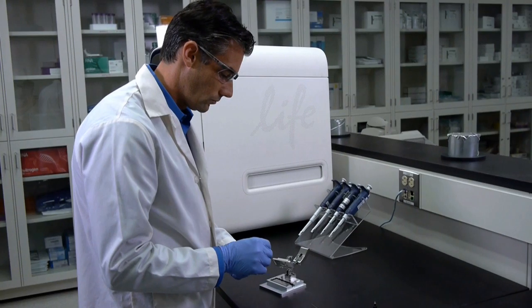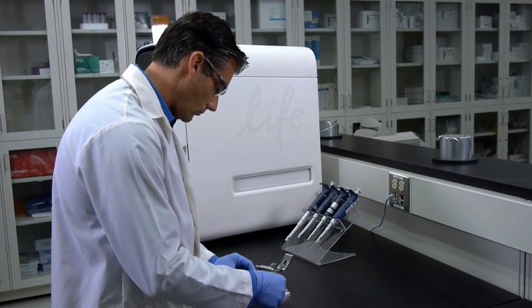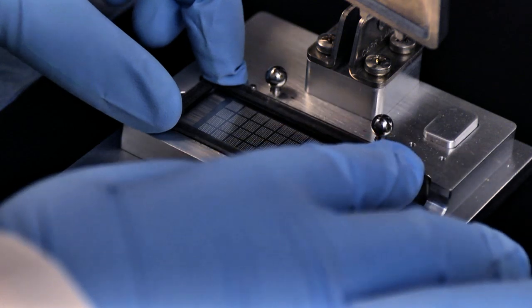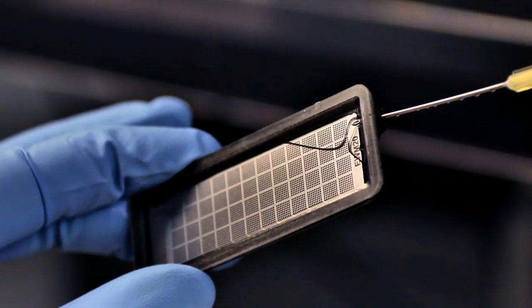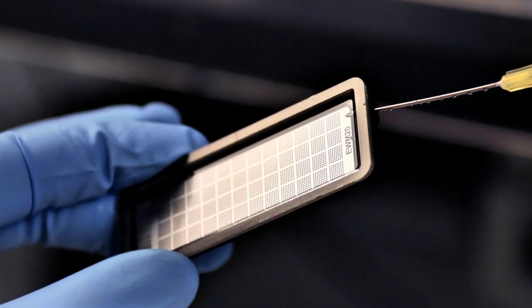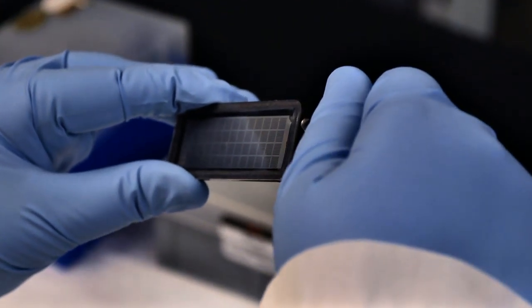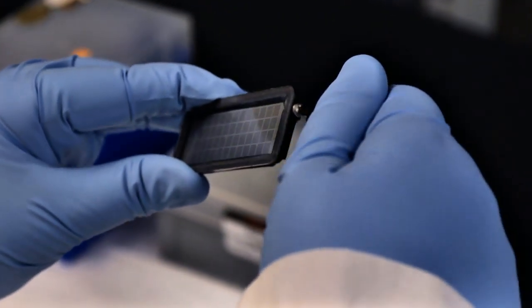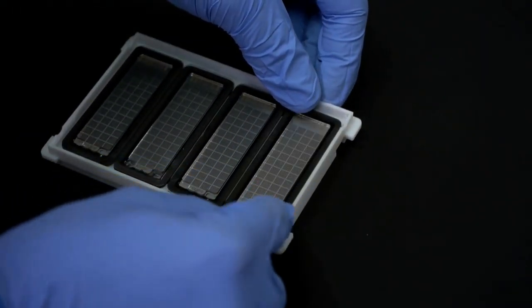The OpenArray workflow saves time and resources compared to running experiments in multiple 384-well plates. Simply seal the plate, add immersion fluid, apply the plug, and then place the sealed OpenArray plate in the carrier.